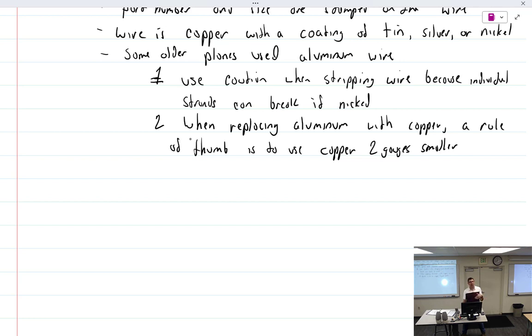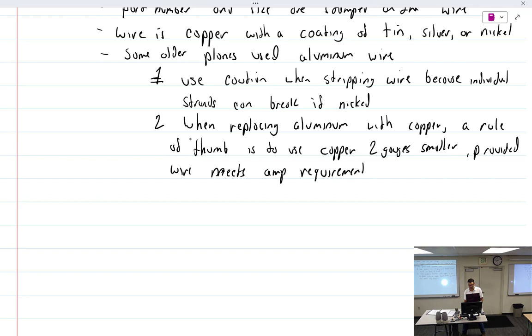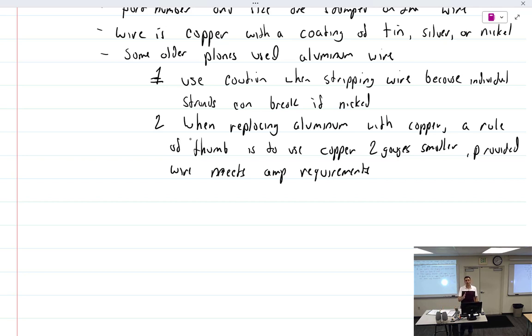Personally, I'd throw out that rule of thumb and use the chart to find exactly what size wire it should be, then cross-check to make sure I'm not going more than two sizes smaller than the aluminum. If the amperage chart said I could go four sizes smaller, I probably wouldn't — I'd go two sizes larger to be safe.